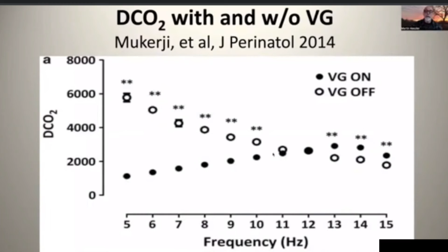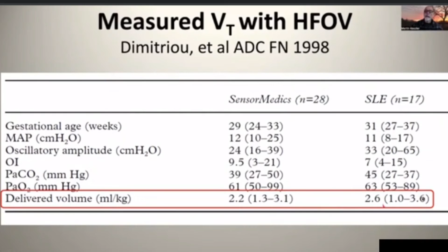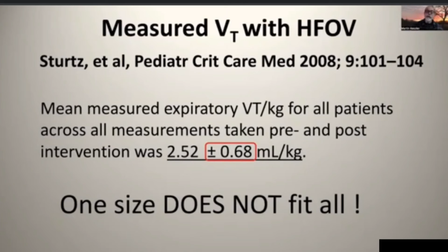There have been some older studies that looked at tidal volume measured with a freestanding hot wire anemometer, and the numbers were typically between 2 and 2.5, with a pretty wide range of observations. Another study more recently also showed a tidal volume of about 2.5 ml per kilo, again with a significant standard deviation, which tells us once more that one size does not fit all. And it turns out that the same variables that affect the need for tidal volume in conventional ventilation also apply in high frequency.